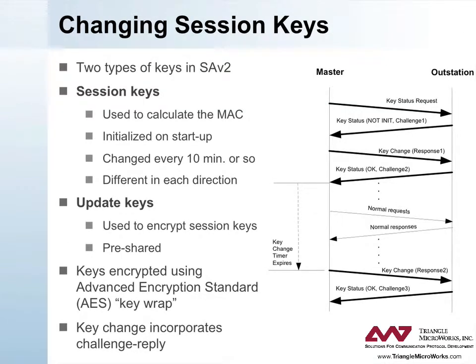There are two types of keys used in basic DNP3 secure authentication, as described in DNP3 SA-V2. Both must be at least 128 bits in length. The session key is the key used in the MAC calculations. A new session key is created every time two devices begin communicating, and is periodically changed by the master. In a typical real-time SCADA system acquiring data from outstations every two seconds, session keys should be changed on the order of every 10 to 15 minutes, perhaps an hour at the most.